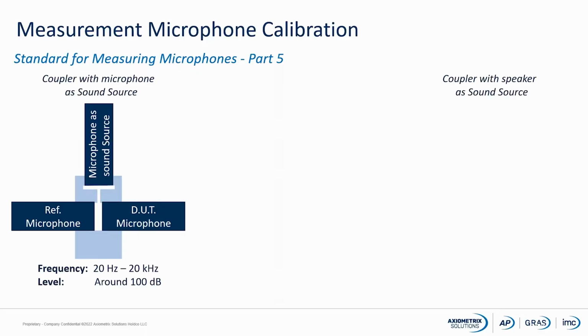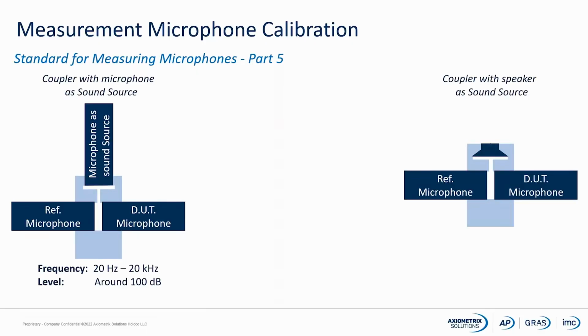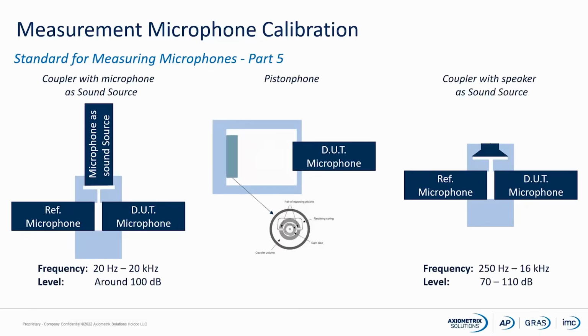We can also have a coupler with a speaker as a sound source. The principle is the same. We can calibrate from approximately 250 Hertz up to about 16K, at levels from 70 to 110 dB in this neighborhood. Most of the secondary laboratories are actually using a piston phone for doing the calibration.